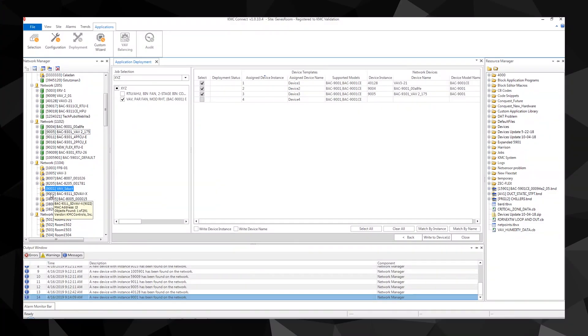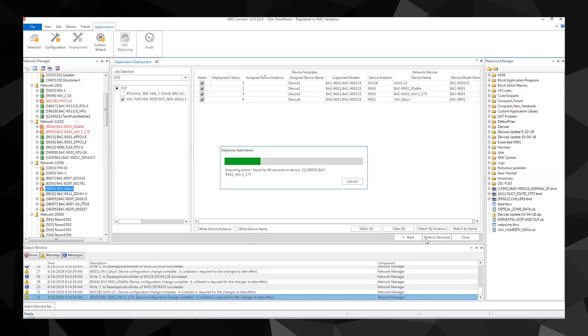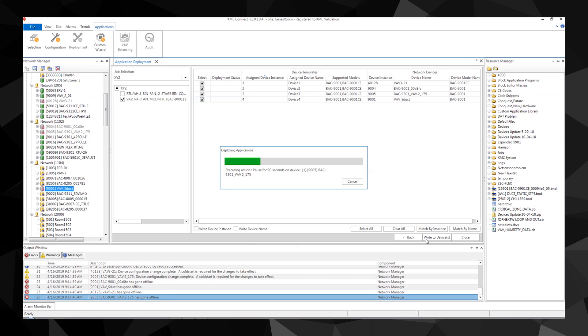Once again, select a job and application from the drop-down menus. This adds the templates to the device template list. The application attempts to match the templates to the controllers on the network manager list. This is done by either the device instance or name. Once this is done, click write to devices. This may take several minutes as the templates are deployed to each matched controller.